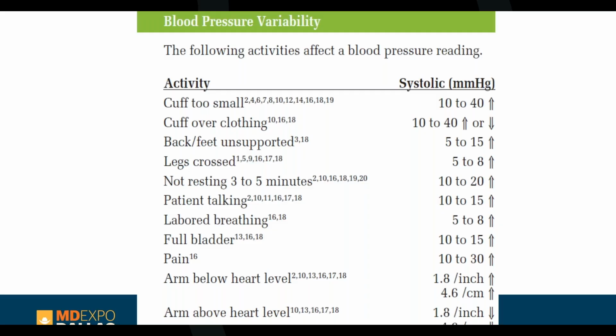Cuff over clothing, 10 to 40, higher or lower. So it's got a lot of variability if it's over clothing. So it should be a bare arm that the cuff is on. Back and feet unsupported, 5 to 15 millimeters. And this should be posted on TechNation TV if you want any of this information. I think you can probably find this if you search Welch Allyn blood pressure variability. It's a Welch Allyn white paper that this is from. Legs crossed, 5 to 8.